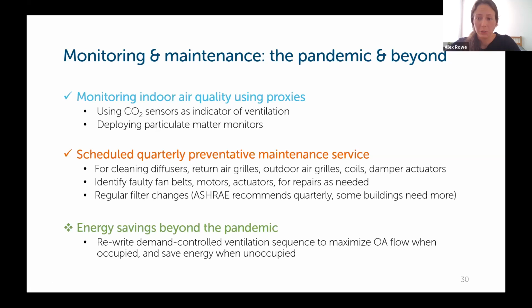And then bringing this back to Efficiency Vermont's more traditional role, this customer has a plan for saving energy when they're no longer in the height of the pandemic and they don't need to operate at maximum ventilation levels. So their intention is to use a demand controlled ventilation sequence once again in their HVAC control system, which will leverage those new CO2 sensors and their variable air volume system to maintain appropriate outside airflow levels when the building and individual zones themselves are occupied, and then save fan energy and heating and cooling energy when the building or individual zones are unoccupied.